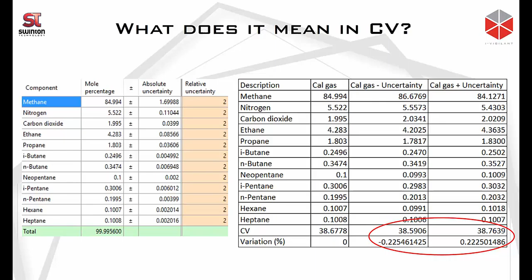So the second source of uncertainty is the uncertainty from reproducibility. What we're doing here is we basically take the daily calibration results, create a control chart, and see the natural variation of the GC, which is measuring the calibration gas in the form of calibration or validation.